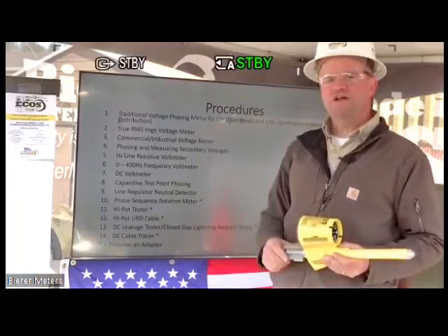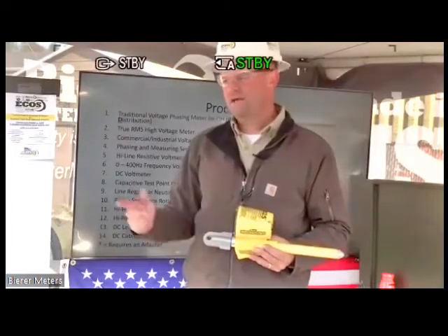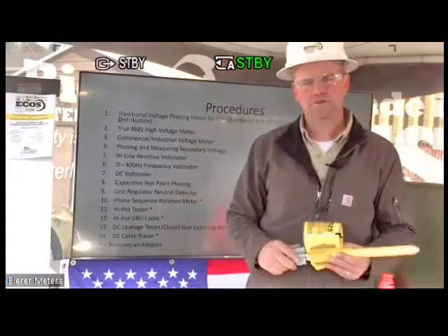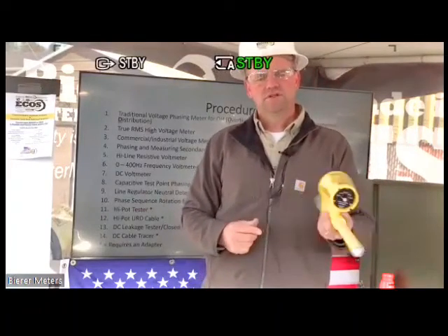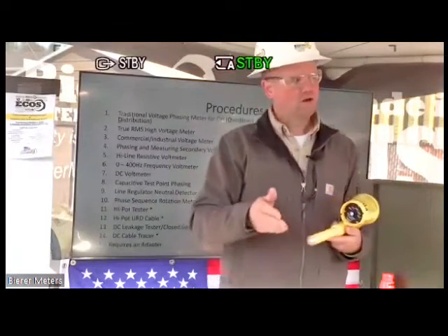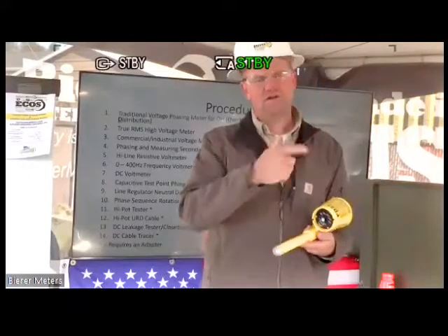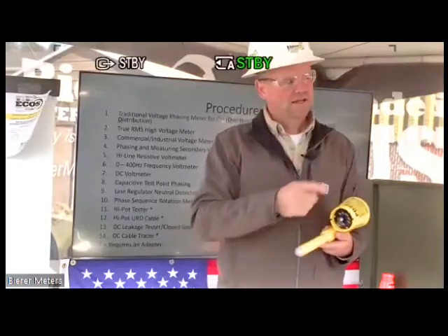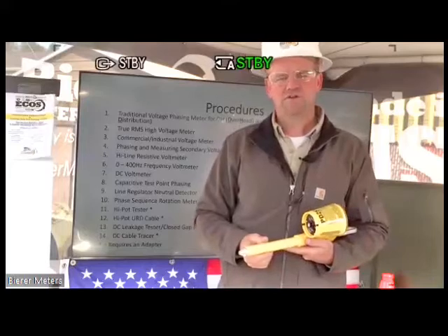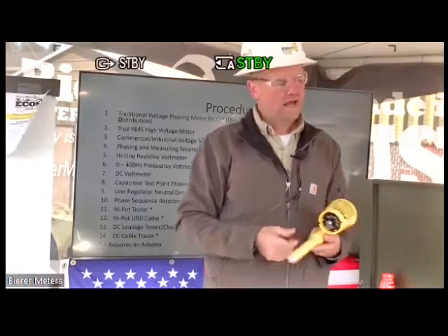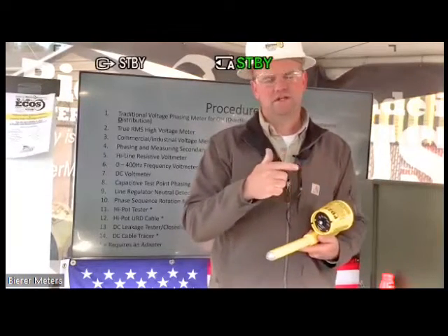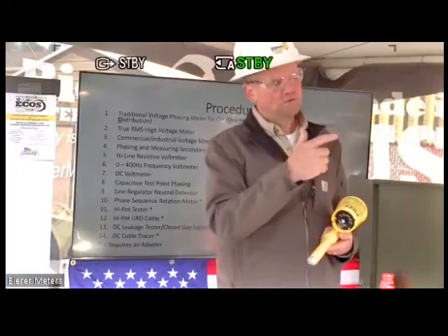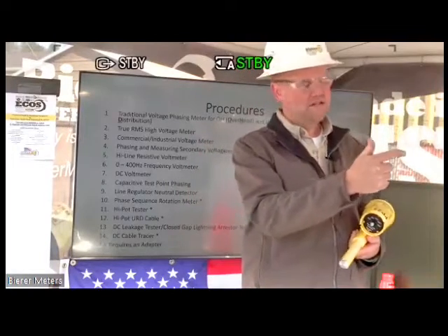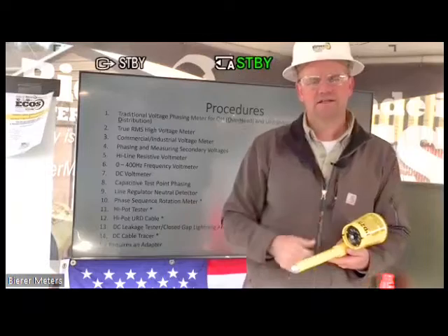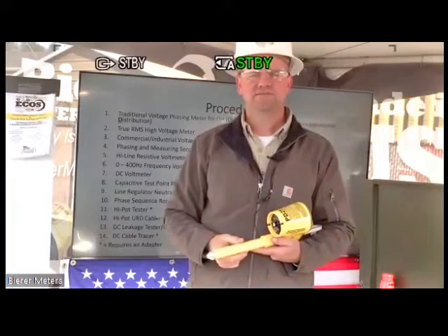And then a DC cable tracer. So a moment ago, I mentioned we had a DC power supply out here. That power supply, if you thread it on one of these probes, and I actually have it threaded on a second probe, and it's in my other three-phase cabinet over here, we'll actually trace that URD cable. Again, it's de-energized, but we'll trace that URD cable over to this cabinet and determine which cable it is.